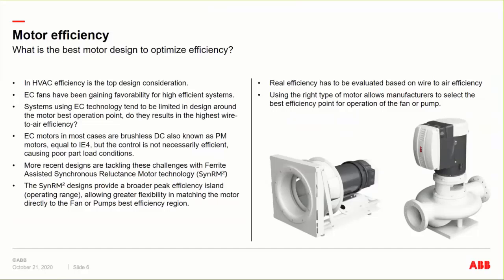So when you're looking at system dynamics, it's not just the motor, because the motor is running variable speed, and then you have a drive on it or a power converter, and how efficient is that power converter at partial loads as well. So you have to look at that in addition to the fan or the pump design. And because of that, we developed this new technology, the SynRM2, second generation SynRM motor.